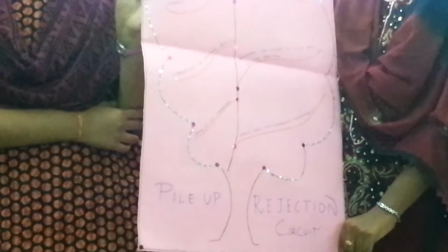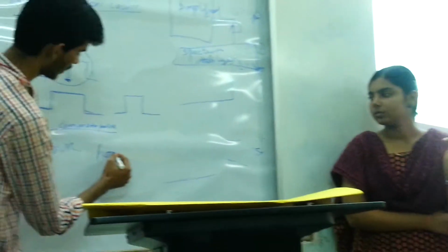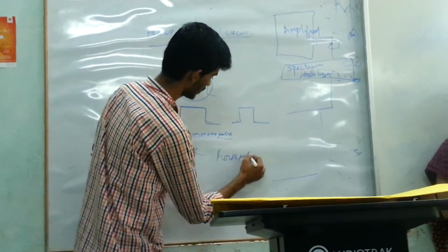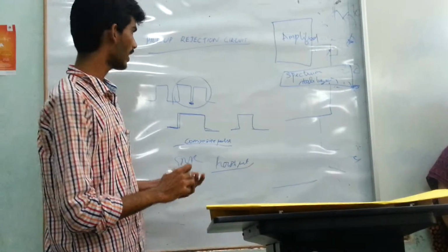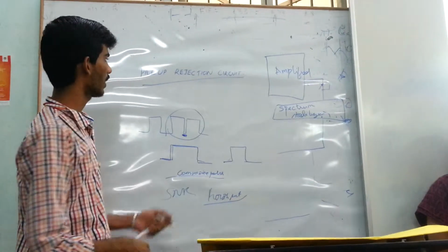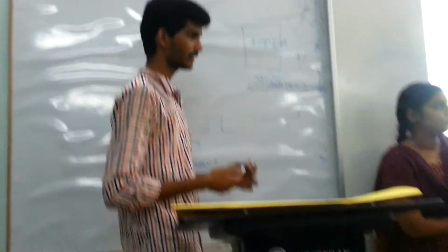By removing the counts from the peaks and adding the counts to the baseline, it affects the spectrum. An ideal pileup detector improves the signal to noise ratio. But the throughput of the ideal pileup detector is lost. So we are going to have a pileup detecting circuit. First, we see about the pileup detecting circuit. Next, we see about improving the performance of pileup detecting.